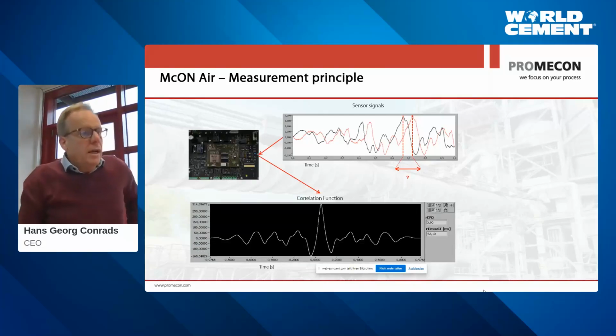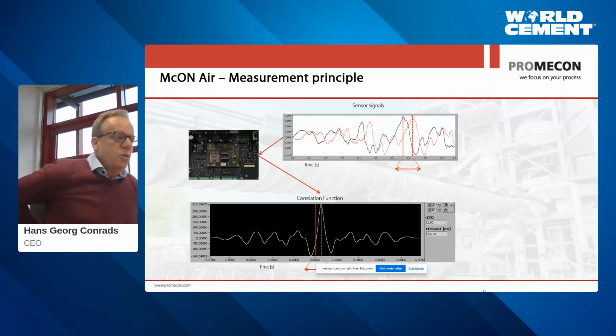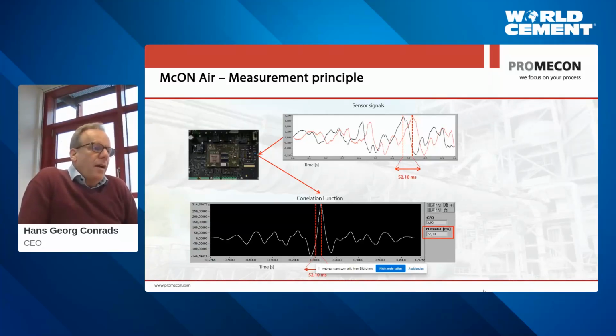Let's have a look at that. We put this into a cross-correlation filter. You look at the cross-correlation function, and here you can see at 52 milliseconds, you have a maximum in overlap between the two functions. And you can see that in the correlation function as a sharp maximum. So here we have our measurement principle. We record the signals on two sensors. We see flow patterns on two sensors. We digitize the signals. We put them into a cross-correlation filter that overlaps those two signals and shifts them in time. And it looks at the relative maximum overlap between the two functions. And this is what you see here. Now, this 52.1 milliseconds in this example represents the time shift between the two measurement signals, and hence the time of flight of the gas between sensor 1 and sensor 2.